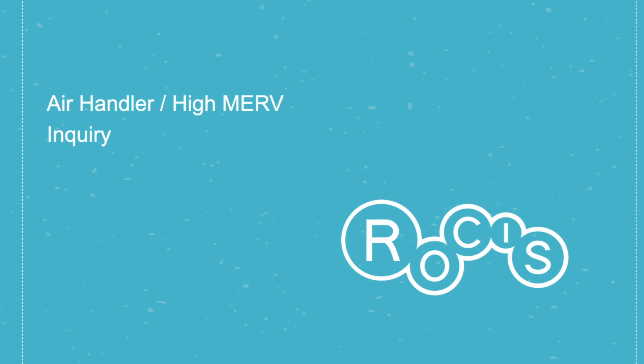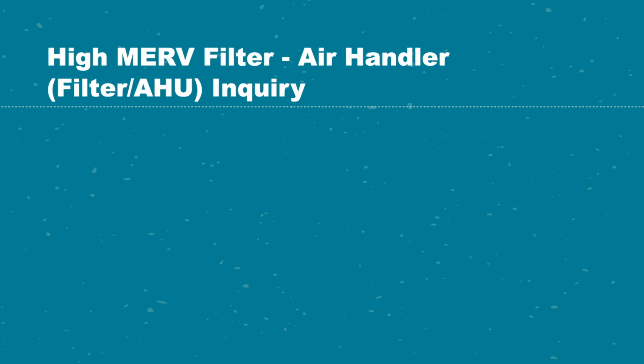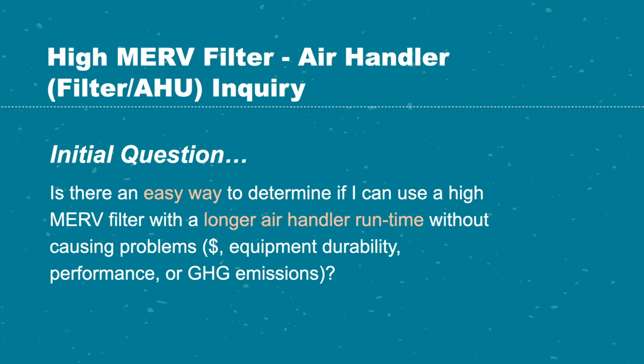We were aware, and the energy efficiency folks have been aware for a long time, that high MERV filters can reduce particles. There's also significant concern that high MERV filters are not appropriate because they are too restrictive. So our initial question was, is there an easy way to determine how you tell somebody whether or not they should use a high MERV filter with a longer air handler runtime, 24/7 or even 50/50, without creating problems? So that's what we set off to answer.